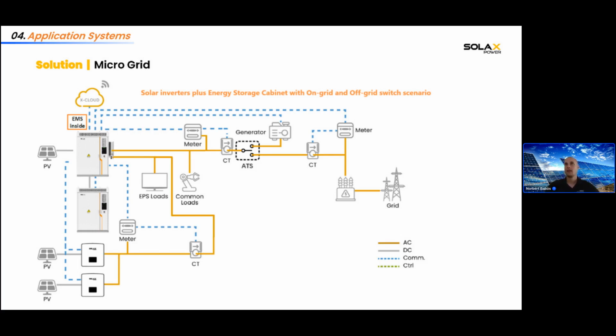So in this case, you can also harvest the PV power from the old string inverters and whatever old inverters you have installed, and you can supply even the EPS loads in a power outage situation. And also, of course, you can have a diesel generator installed with the EMS. So in this case, all of the connections will go to the EMS, and then the EMS will decide and control all of the power generation and distribution.